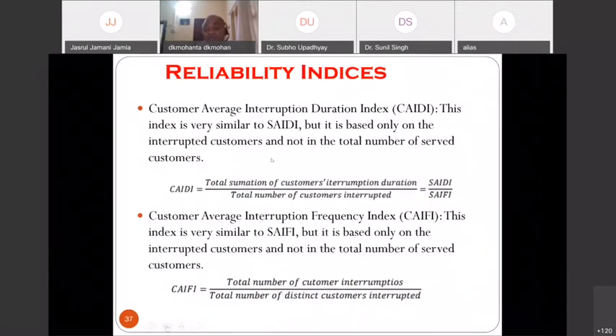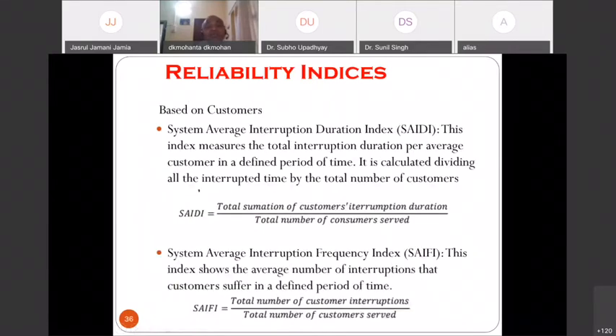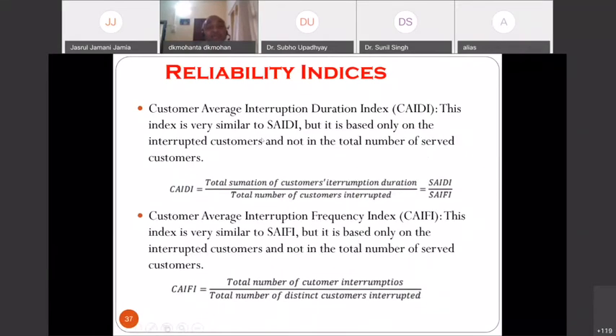These other terms are from the customer perspective rather than the system or microgrid perspective. From the customer perspective, we have the customer average interruption duration index, or CAIDI. This index is very similar to SAIDI, but it's based on the interrupted customers rather than the total number of served customers.